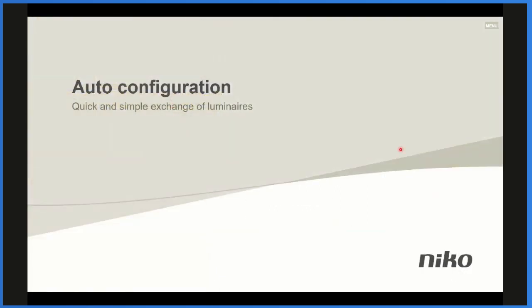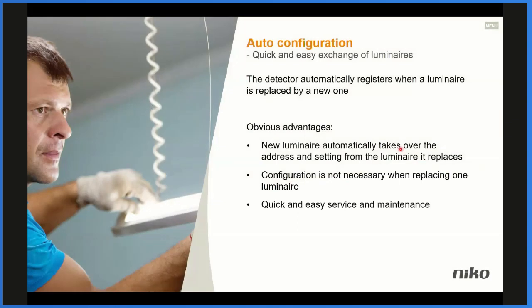The most popular, so to speak, functionality that we have is the auto configuration. That means that the new luminaire automatically takes over the address and the settings set from the luminaire that is replaced due to broken or whatever. It is not necessary to make a new configuration when replacing one of the luminaires. And for the end user, that means it's a quick and easy service and maintenance of the lighting system.